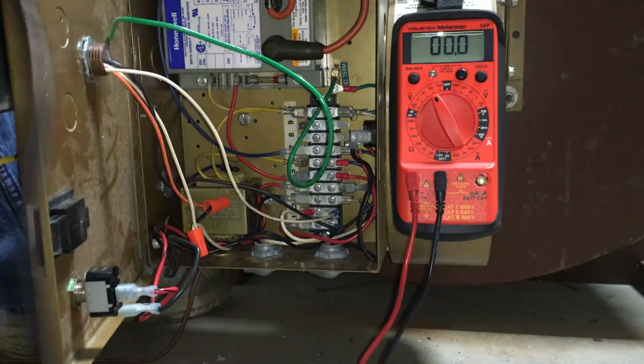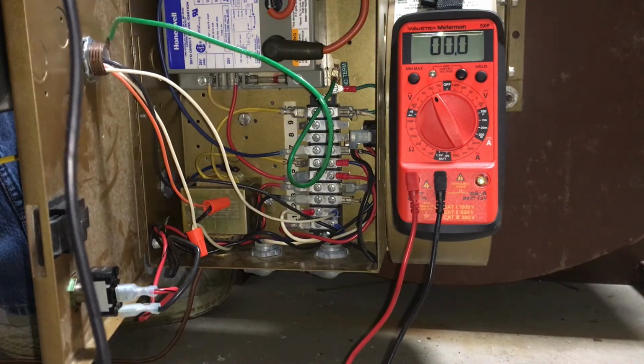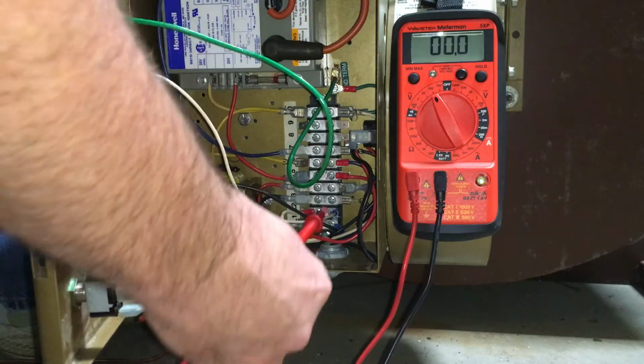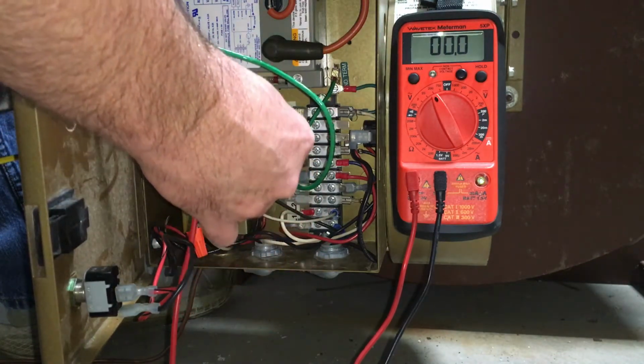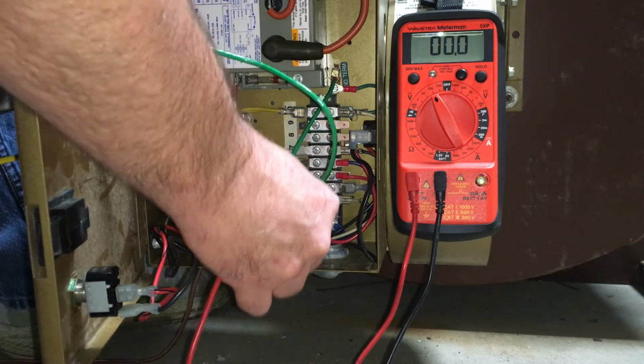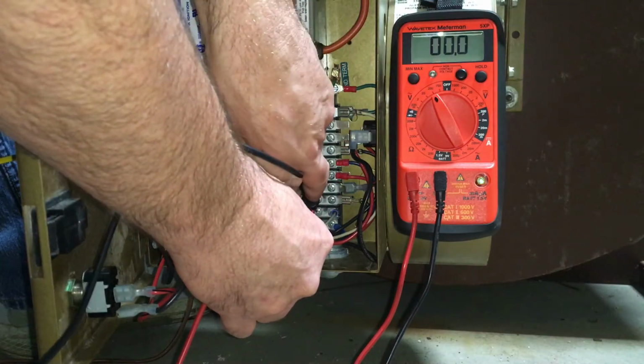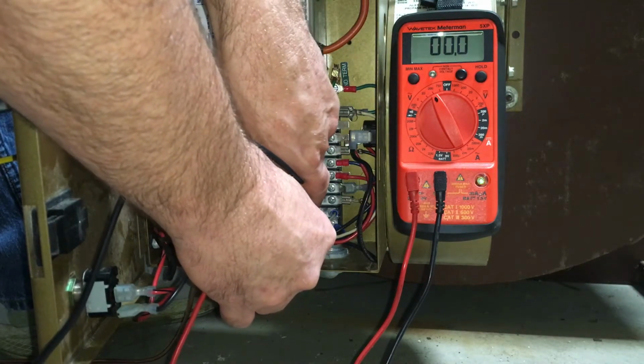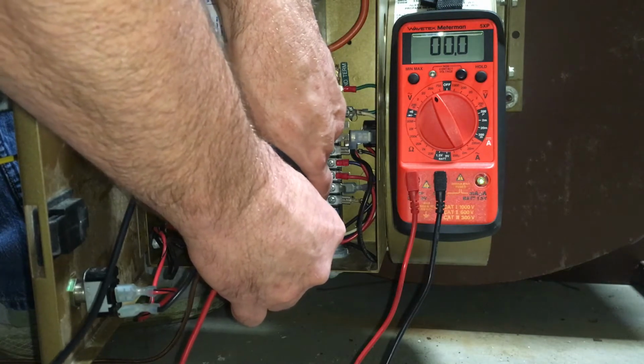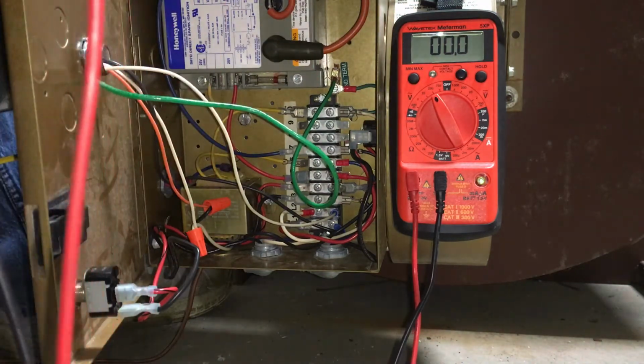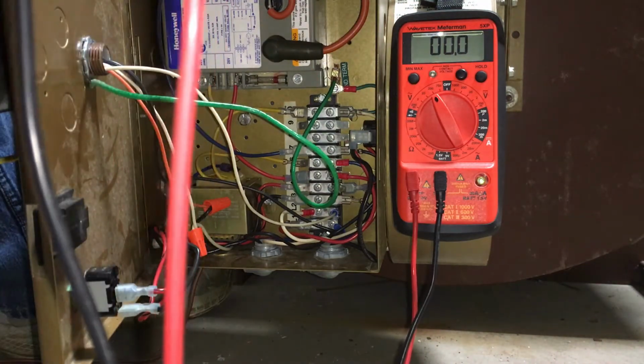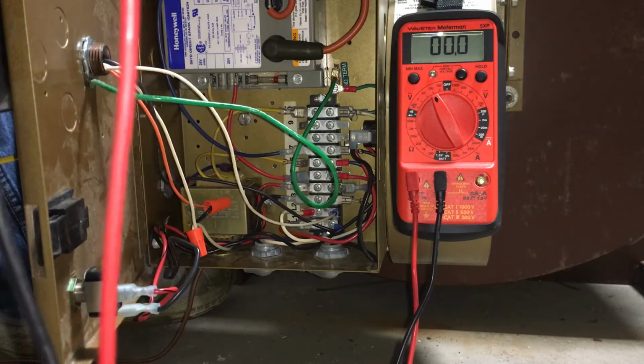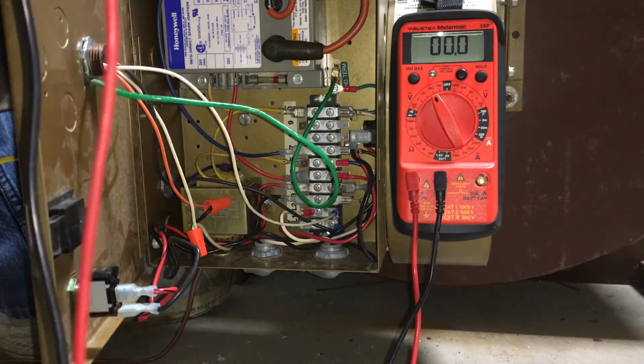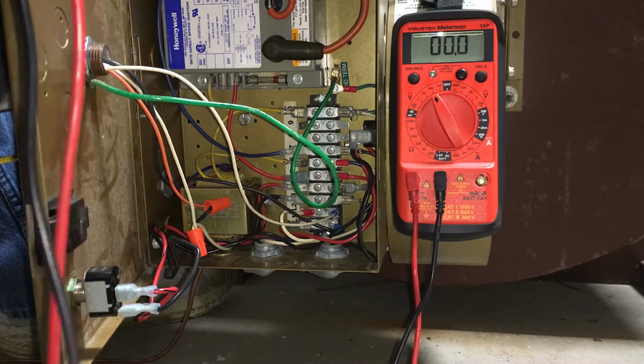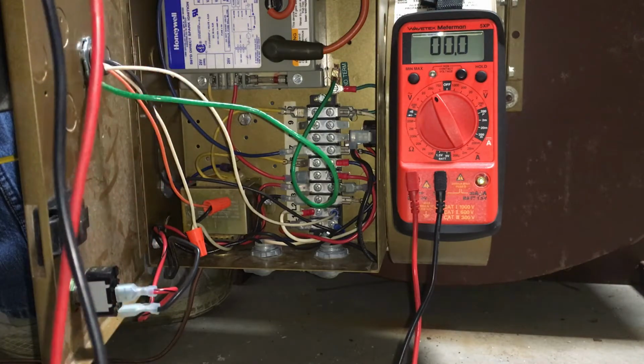So, as it says, L2 and L1, verify voltage. You can see the terminals are labeled right here in the control box. So you have L1 and L2. And you can see on my voltmeter that we do not have any voltage going through there. We are set for 200 volts AC. This system is wired up for 115 volt. There are also units that run on 230 volt as well. But for this particular model, we will look for 115 volt.